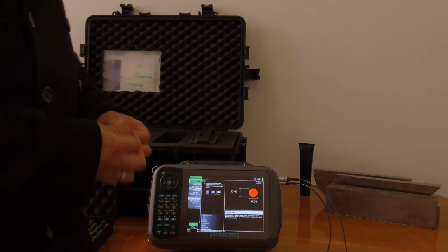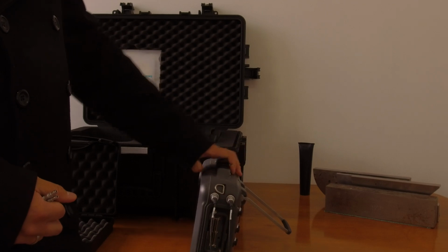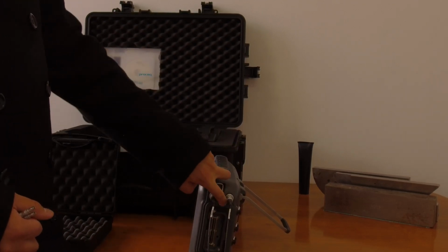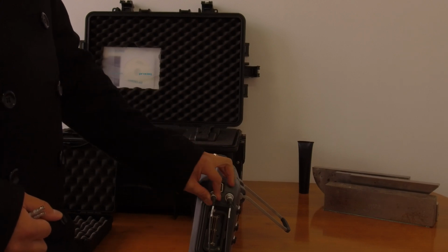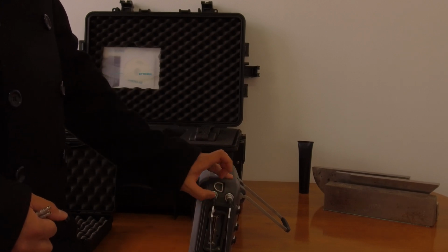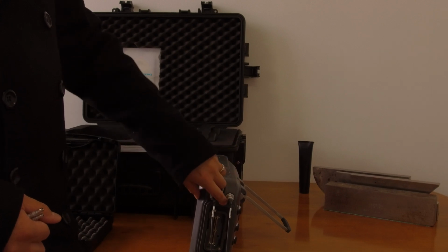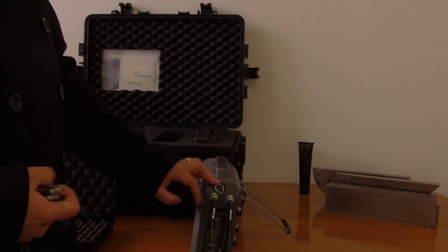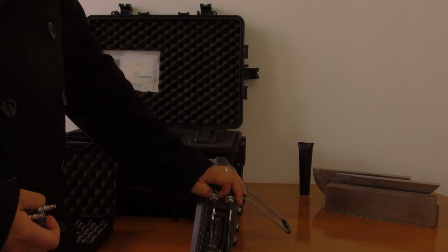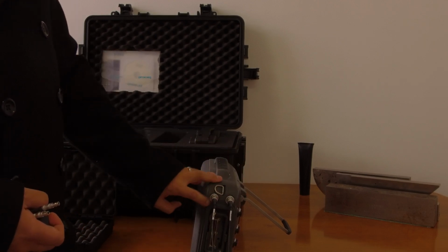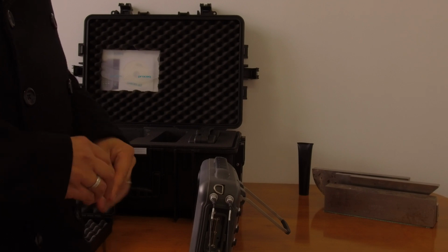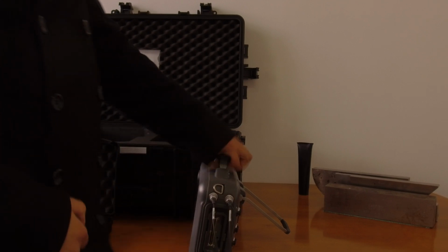Normally you're looking at either a T or a red dot or something like that. Okay, and then if you did get an indication of that, you would have a look at the side here and you would see that one side says transmit/receive. So that's for any monocrystal or single crystal. And then you see one side has receive. So if you did have one that indicated to you which one was transmitting, you would connect it to this one here that says T/R. Okay. In this instance, this probe doesn't differentiate between either side, so it doesn't matter too much.